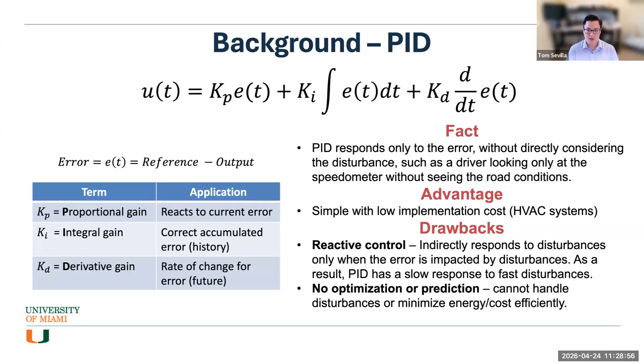I'll talk about that in the next part, where time of use, or TOU, operation becomes tricky. Since PID only tracks the set point, there's no awareness of energy pricing in an HVAC system, so TOU savings have to be achieved externally by adjusting the set point. You have to come up with some logic that says between certain thresholds, you want a certain set point, then you read the pricing dynamics and adjust your set point based on that.